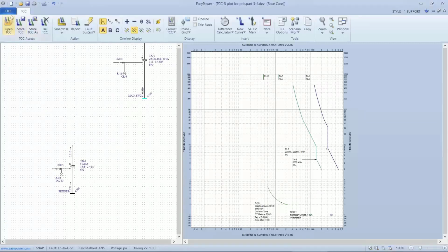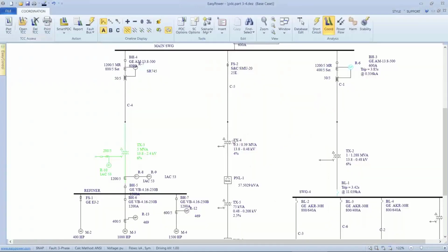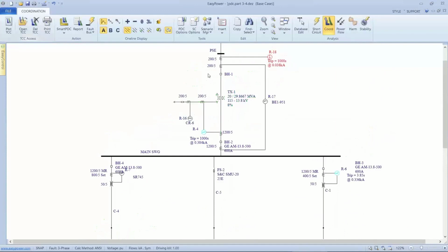So if we go back to how to do this in EasyPower, the issue is the relay can be sensitive to a very small differential between the upstream current and the total sum of the downstream current, and consequently be able to determine a fault much sooner, long before the full current even hits the relay or the transformer. So that small differential in current, whatever it is that's been determined by the designer, will trip the device, and the device will then open the breaker long before it hits the maximum fault current that we've set up the overload relays for. Well, EasyPower can't simulate what that small differential is.